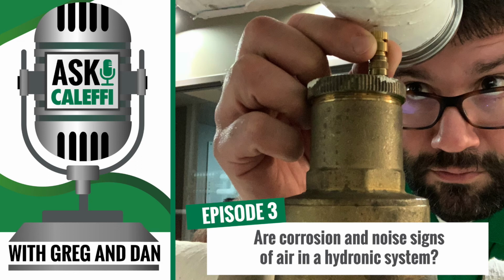Your inlet and outlet are typically coming in at different levels of the air separator, and it's designed to run at a higher velocity. You're looking at 8 to 10 feet per second on something like that, versus a standard, which is right around 4 to 6. With our bodies being so much larger, we're creating that instant velocity drop, so we don't have a pressure drop through ours. At 4 feet per second, 8 feet per second, we're still in pretty good shape.